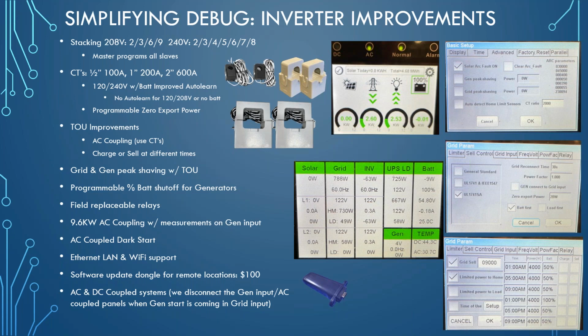And next up, we've got some time of use improvements. You can AC couple using the CTs, which are the current transformers, these sensors here, and you can charge and sell at different times. Basically, if you have a rate structure where you're billed a different amount at different times, and you want to discharge your battery when it's more expensive to buy power from the grid, or any other situation, maybe you have peak shaving or peak demand pricing or anything like that, you can program the system to discharge at a certain rate at a certain time on a particular day of the week. You can get that specific with it if you like in the settings. And again, we do have a separate document for exactly how to do that.